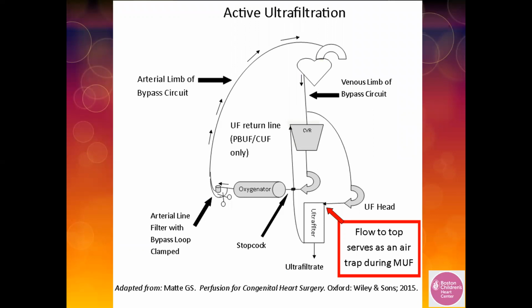This setup is a variation of the technique first described by the Halifax, Nova Scotia Perfusion Group back in the year 2000. To note, there is no possibility of this head pulling air across the hollow fiber membrane oxygenator. Any negative pressure would be exerted on the venous line and would therefore pull from the venous flow or the reservoir through the venous straw connection. Using this arrangement allows one to utilize a single, consistent method of active ultrafiltration throughout the case without relying on a system pressure and the variable shunt that can occur with passive ultrafiltration.